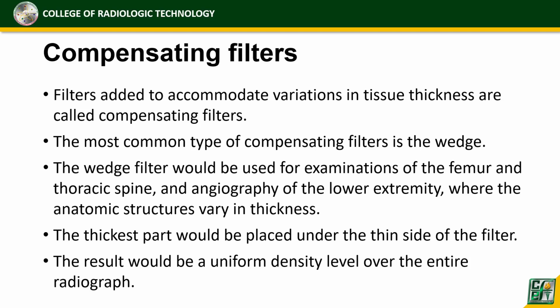And now we go to the compensating filters. Okay. So filters are added to accommodate variation in tissue thickness. Okay, these are called compensating filters. So most common type of compensating filters, yung tinatawag na wedge filter. Okay. So the wedge filter would be used for examinations of the femur, the thoracic spine, okay, and angiography of the lower extremities.